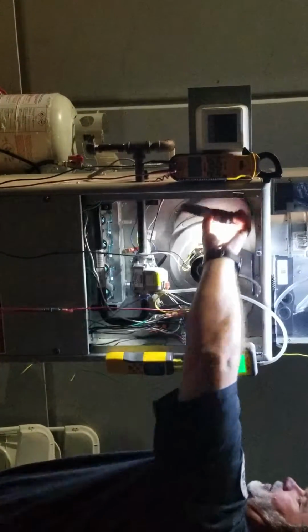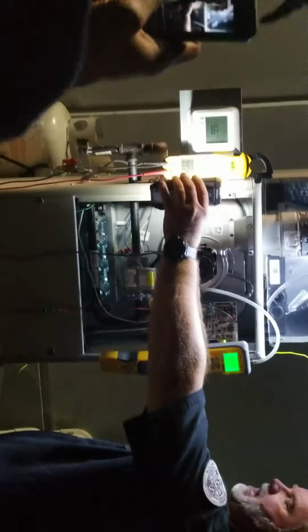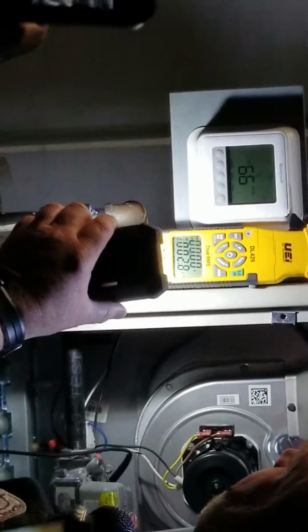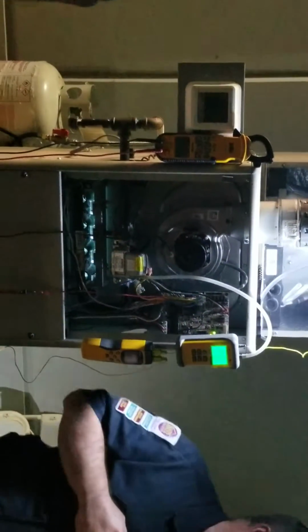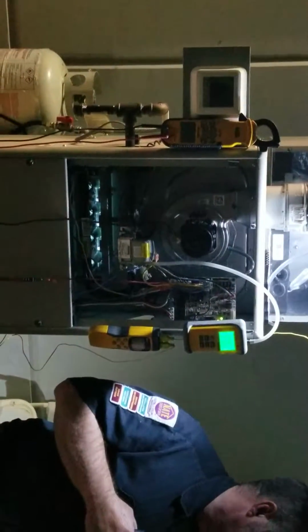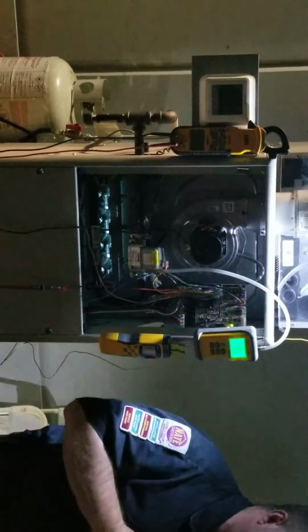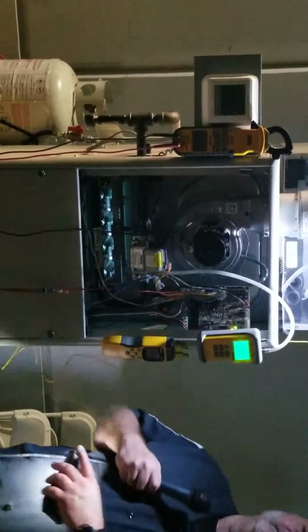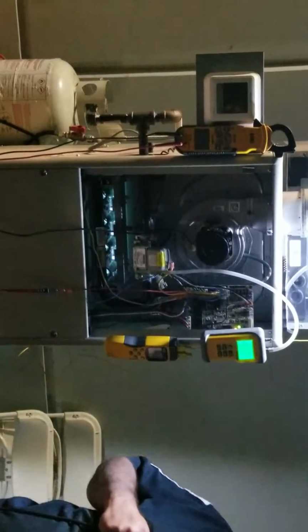Now, if you look at my meter here, can you see what the reading is on the meter for the microamps? Is it on microamps? 2.8. Yep, 2.7, 2.8. That's 2.7 microamps. It only needs 0.5, guys. It's putting out 5 times as much as it needs. Does that make sense? If I got that kind of reading on my meter and my board was telling me there was a problem, tell me what do you think it would be?